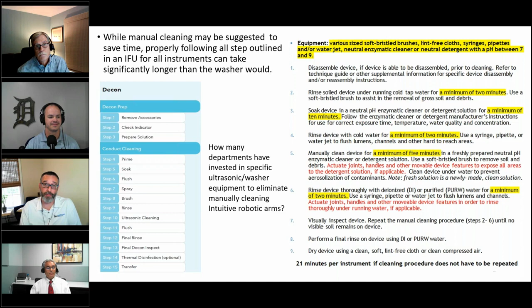And then the other thing is, and this goes along with the preferred, and like I said, this is a little thing that's actually from the Intuitive IFU to talk about some of these steps: prime, soak, flush. The reason that we've got ultrasonics with pulse flow and things like that, and needing that lumen testing like Kevin talked about, is because that's integral to that piece of equipment cleaning that device properly. So we invest in this equipment for its repeatability, for its consistency, and for it to help us. And so you should really take a pause before you say, yeah, I'm gonna skip this very helpful piece of equipment and I'm just gonna do it by hand. There should be a good reason for it, and you have to know that you're prepared to do it if you're going to make that choice.